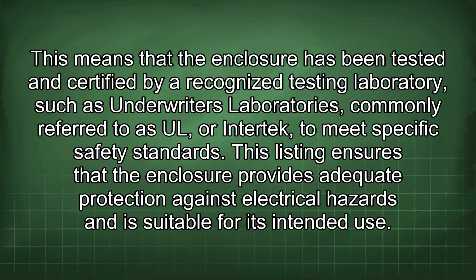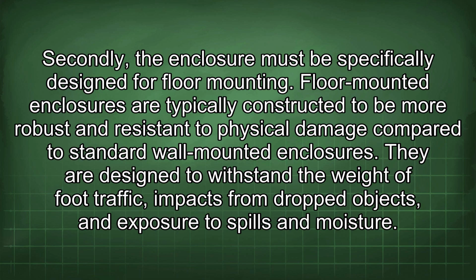This means that the enclosure has been tested and certified by recognized testing laboratories such as Underwriters Laboratories, commonly referred to as UL, or Intertek, to meet specific safety standards. This listing ensures that the enclosure provides adequate protection against electrical hazards and is suitable for its intended use. Secondly, the enclosure must be specifically designed for floor mounting. Floor-mounted enclosures are typically constructed to be more robust and resistant to physical damage compared to standard wall-mounted enclosures. They are designed to withstand the weight of foot traffic, impacts from dropped objects, and exposure to spills and moisture.